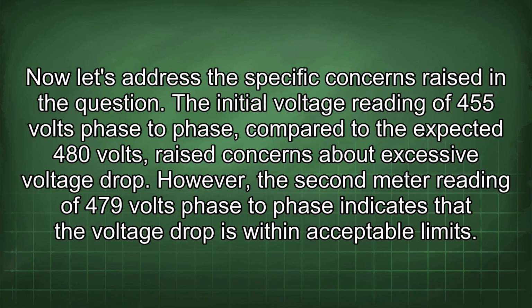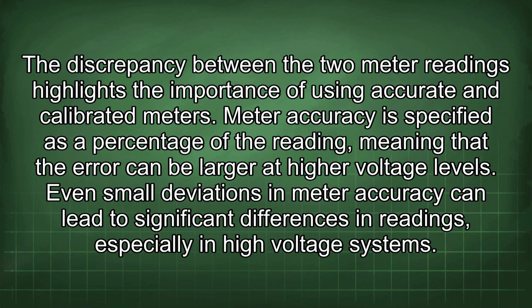Now let's address the specific concerns raised in the question. The initial voltage reading of 455 volts phase-to-phase compared to the expected 480 volts raised concerns about excessive voltage drop. However, the second meter reading of 479 volts phase-to-phase indicates that the voltage drop is within acceptable limits. The discrepancy between the two meter readings highlights the importance of using accurate and calibrated meters.